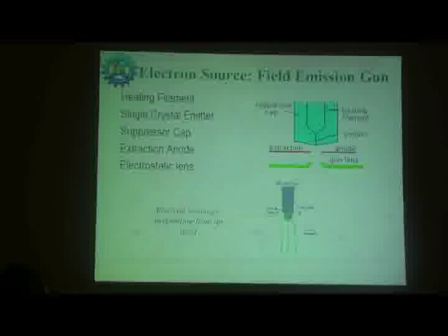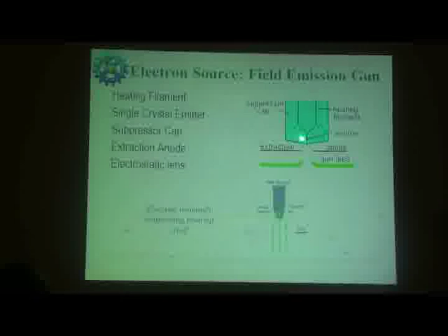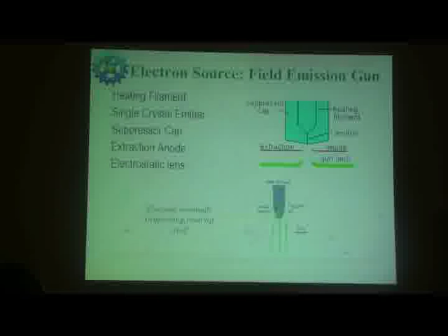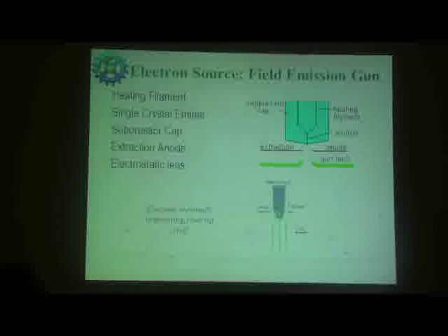The next one is the field emission gun. You know that if you apply a very high field between a sharp tip and the anode, you can tunnel the electrons. Suppose you have a sharp tip, like 10 nanometers, of a tungsten crystal, and you apply a very high potential between this tip and the anode. Because the tip is sharp, the field will be very high. The smaller the tip, the larger the field. So you apply something like 30 kilovolts, the field will be very high, the electrons will be tunneling and coming out of the gun. That is how the electron source is generated from the field emission gun.